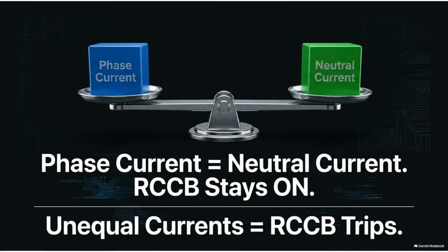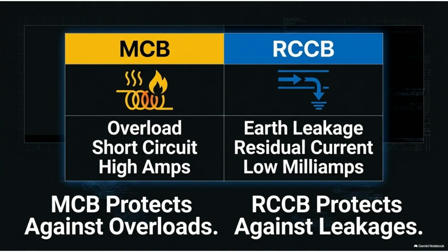Let's look at why. An RCCB monitors current balance. If the phase current equals the neutral current, the device stays on. However, if they are unequal, indicating leakage, the RCCB trips. It is important to distinguish between circuit breakers. An MCB protects against overloads and short circuits involving high amps. An RCCB is designed to protect against earth leakage and residual currents, operating at much lower levels.